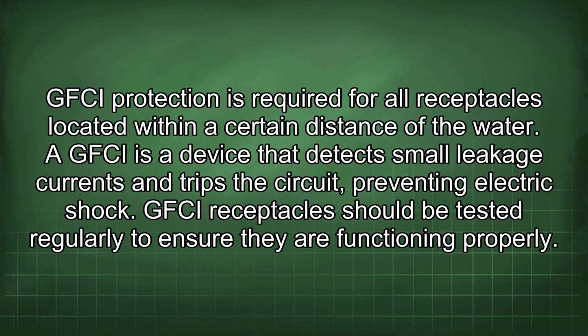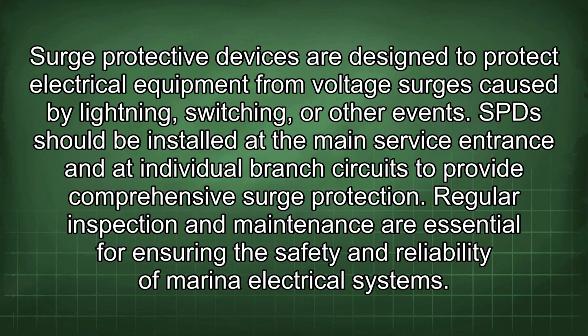GFCI protection is required for all receptacles located within a certain distance of the water. A GFCI is a device that detects small leakage currents and trips a circuit, preventing an electric shock. GFCI receptacles should be tested regularly to ensure they are functioning properly. Surge protective devices are designed to protect electrical equipment from voltage surges caused by lightning, switching, or other events. SPD should be installed at the main service entrance and at individual branch circuits to provide comprehensive surge protection.